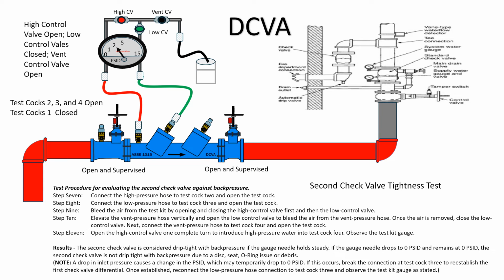Test procedure for evaluating the second check valve against back pressure. Second check valve tightness test, DCVA. Step 7. Connect the high-pressure hose to test cock 2, and open the test cock. Step 8. Connect the low-pressure hose to test cock 3, and open the test cock. Step 9. Bleed the air from the test kit by opening and closing the high control valve first, and then the low control valve. Step 10. Elevate the vent pressure hose vertically, and open the low control valve to bleed the air from the vent pressure hose. Once the air is removed, close the low control valve.